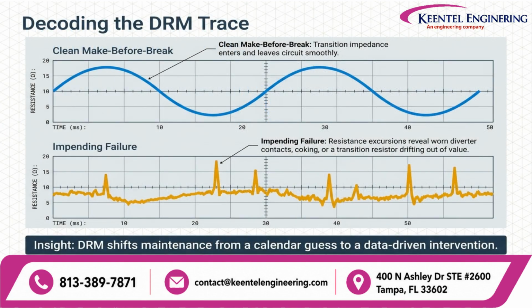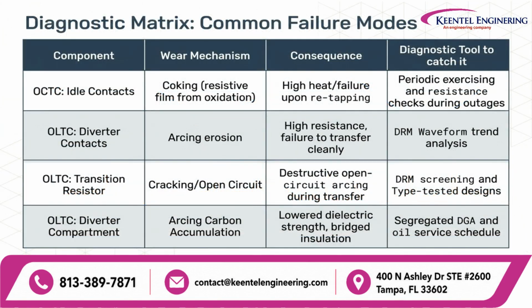Dynamic resistance measurement provides one of the most powerful diagnostic tools for OLTC health assessment. A healthy DRM trace shows smooth resistance transitions during each tap change. As contact wear increases, resistance begins to fluctuate, producing spikes and irregular patterns. These abnormalities may indicate contact erosion, poor alignment, contamination, mechanical wear, or transition resistor deterioration. Rather than relying solely on calendar-based maintenance, DRM enables predictive maintenance by identifying problems before they result in unexpected transformer outages. Every major OLTC component has characteristic failure mechanisms.